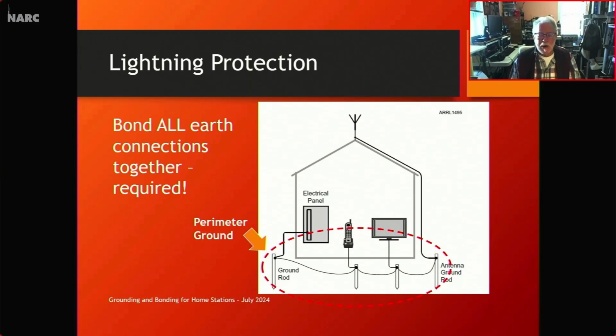And that is not at all unusual if you have a nearby lightning strike to have 1,000 amps for a short period of time flowing through the soil. So 10 or 20 ohms times 1,000 amps is 10 or 20 kilovolts. And that's what would be the voltage difference between, say, my electrical service and my telephone system when there was a nearby lightning strike. And that would generally be enough to blow up my telephone system.